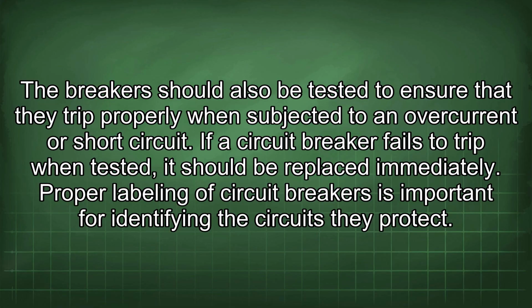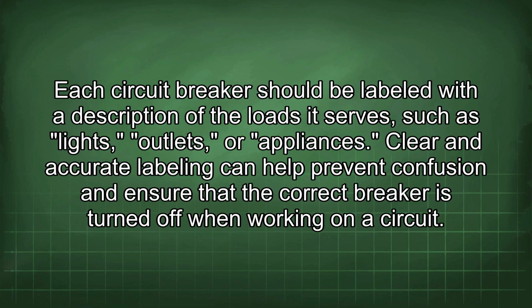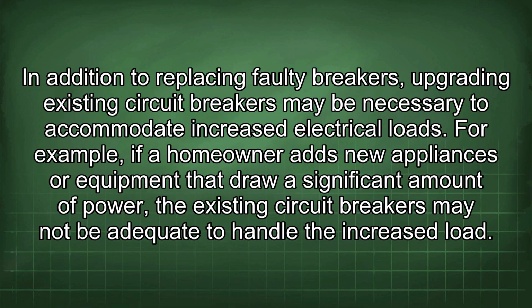Proper labeling of circuit breakers is important for identifying the circuits they protect. Each circuit breaker should be labeled with a description of the loads it serves, such as lights, outlets, or appliances. Clear and accurate labeling can help prevent confusion and ensure that the correct breaker is turned off when working on a circuit. In addition to replacing faulty breakers, upgrading existing circuit breakers may be necessary to accommodate increased electrical loads.